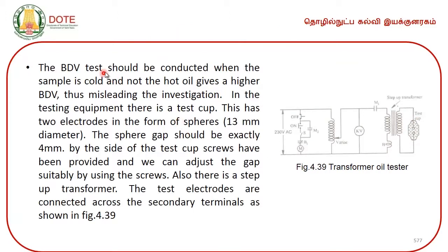The BDV test should be conducted when the sample is cold and not hot, as hot oil gives a higher BDV, thus misleading the investigation. In the testing equipment, there is a test cup. This has 2 electrodes in the form of spheres. One is 13 mm in diameter. The sphere gap should be exactly 4 mm by the side of the test cup.